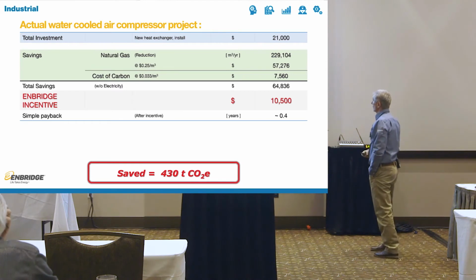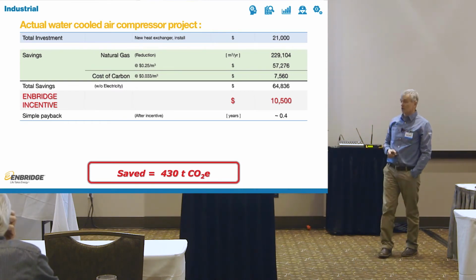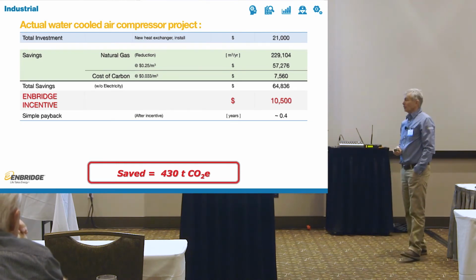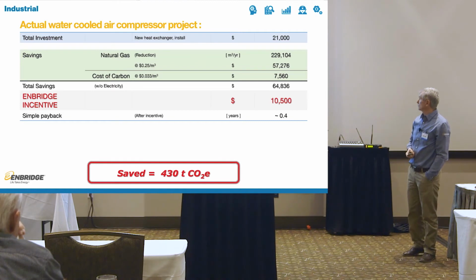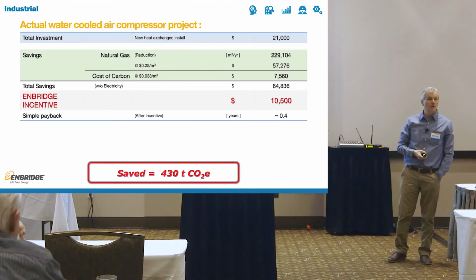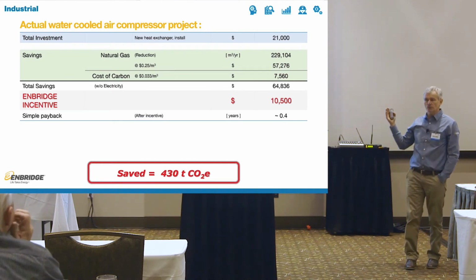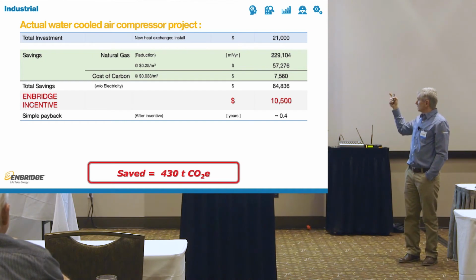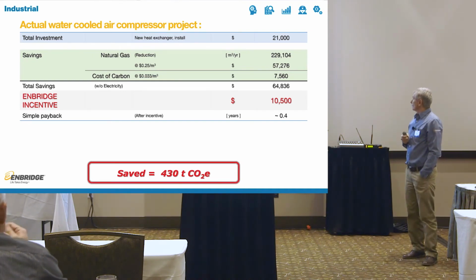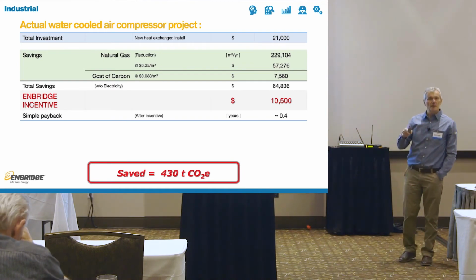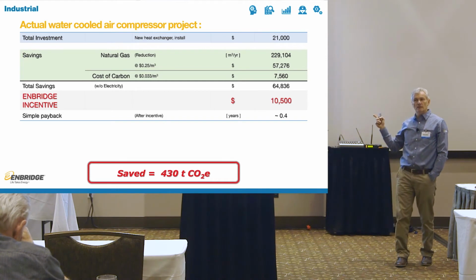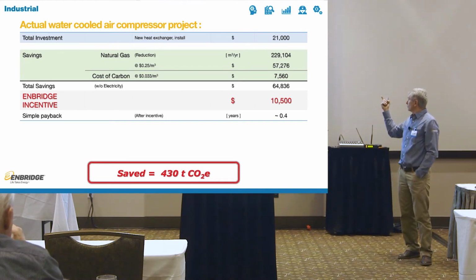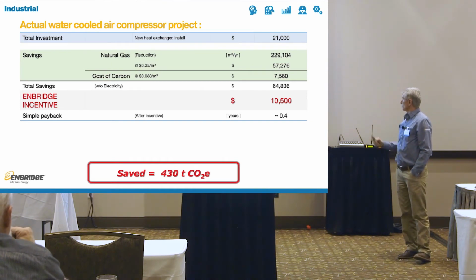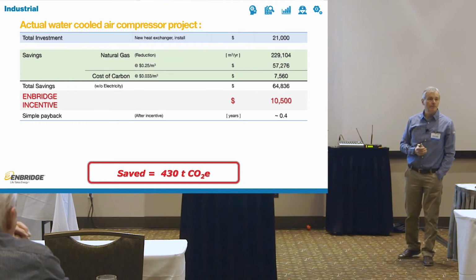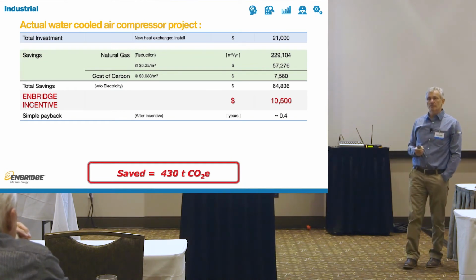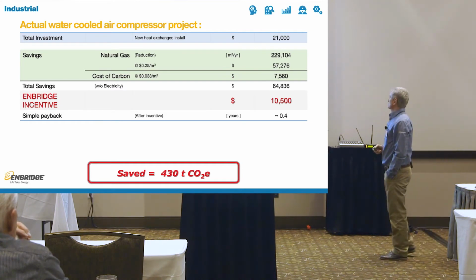So they did that. They had a heat exchanger on the books. They installed it themselves for $21,000, heat exchanger and installation. They saved 230,000 cubic meters a year. That equates to about $65,000 in savings. That doesn't count any savings from the reduced cooling tower load, but it does account for all the savings in natural gas. So instead of using 230,000 cubic meters of natural gas to preheat the makeup water for the boiler, they just use the waste heat that they already paid for anyway. We gave them $10,000 in incentive, 50% of the project cost, and the payback was 0.4 years. It's sometimes as simple as that. 430 tons of CO2e was saved.